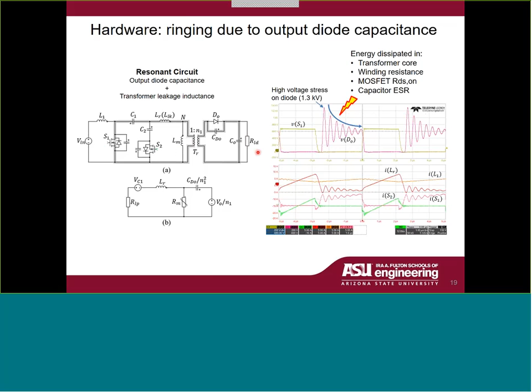So there is a problem for 2 reasons. One is the very high voltage stress. We are actually using 1.2 kV devices, and the device survived even 1.3 kV application for a fairly long duration. But obviously, we don't want to operate that way. It's not reliable. So that's one main reason. The second one is the losses associated with that. The damping is mainly done by the extra high frequency current through the core. This core loss is modeled by this resistance, and that is where much of the damping happens. So we observed losses of almost 1% because of this resonance phenomenon.